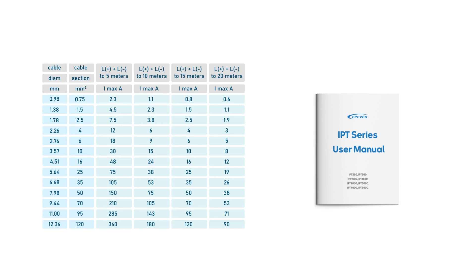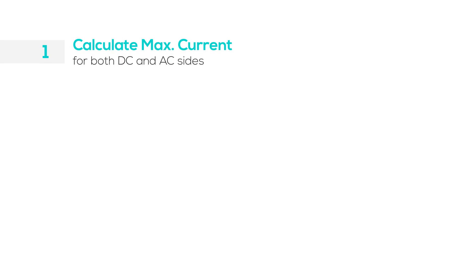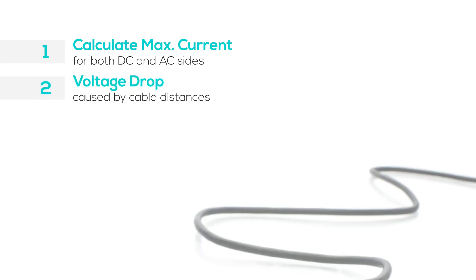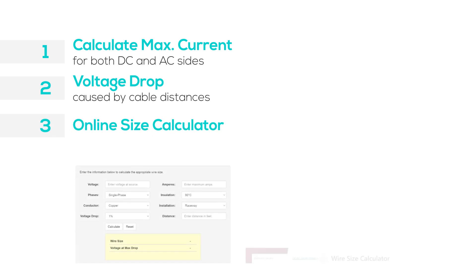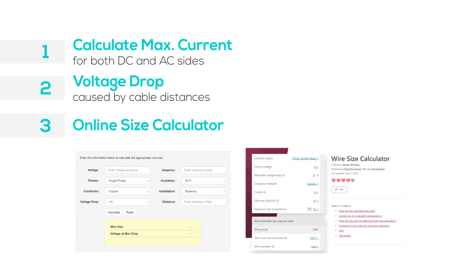Always start with product manuals and wire sizing charts as reference points. If calculating on your own, calculate current for both DC and AC power to find the maximum current. Voltage drop also matters — strive for a voltage drop below 3% for DC and 5% for AC. Online calculators can help you decide the right wire size — you'll need parameters like system current, input or output voltage, distance, voltage drop, and ambient temperature.